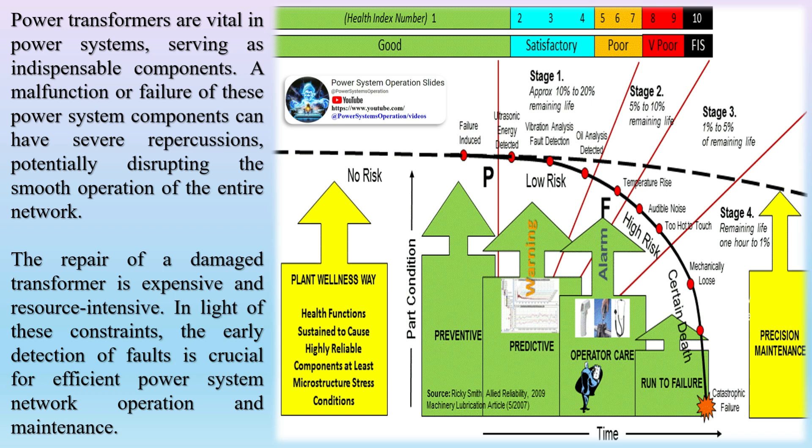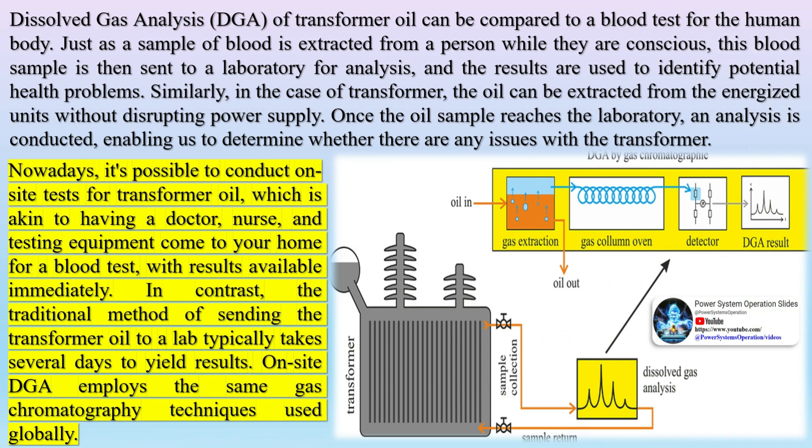In free breathing transformers, degassing or gas dissolving can occur over time, which may influence the interpretation basis of the DGA. The reason for this is that molecules always strive for equal distribution in a chemical physical system. Various theories, which are based on the determination of physical and chemical material properties, can be used to describe these processes.